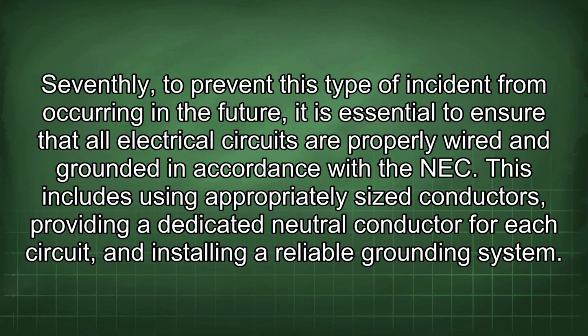Seventhly, to prevent this type of incident from occurring in the future, it is essential to ensure that all electrical circuits are properly wired and grounded in accordance with the NEC. This includes using appropriately sized conductors, providing a dedicated neutral conductor for each circuit, and installing a reliable grounding system.